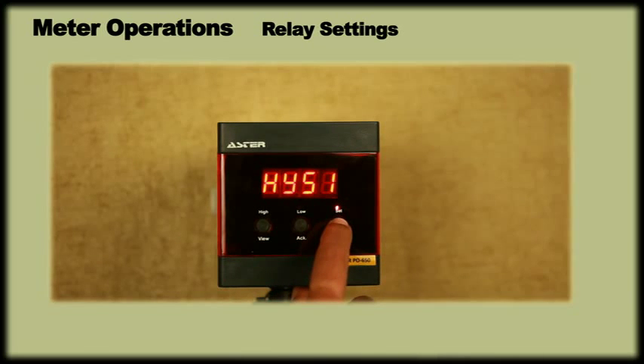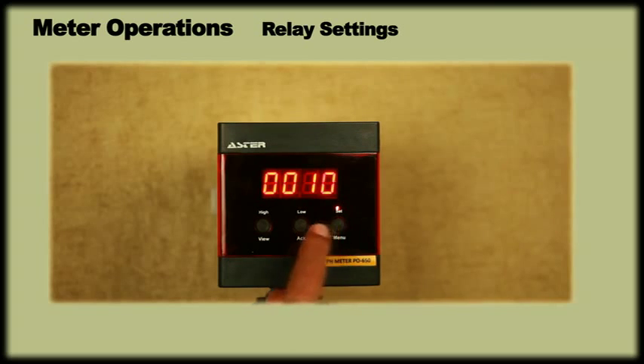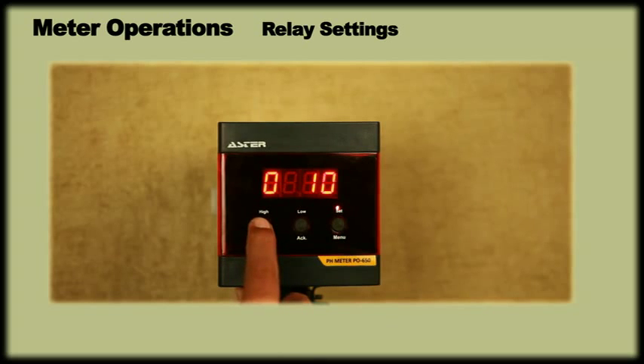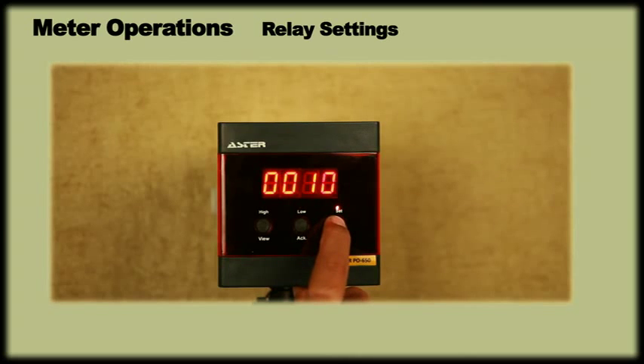The display will now show hysteresis 1. On pressing menu, it will show a previously set hysteresis value. Using ACK key and view keys, we can set the required hysteresis value. Let us set hysteresis value at 10% and press menu to enter. Next, the display shows set low.